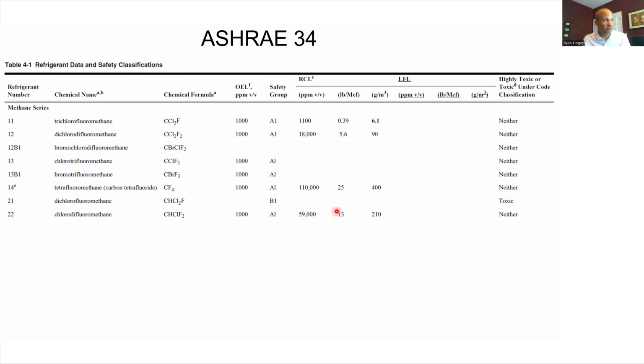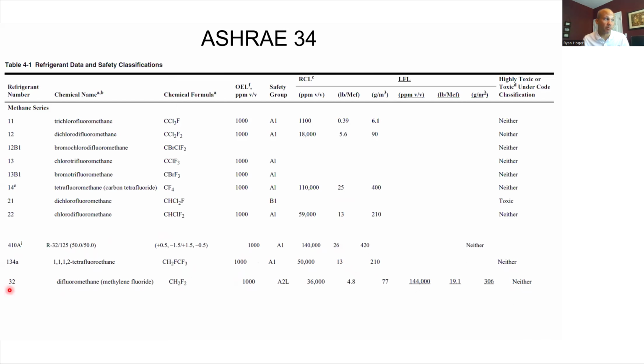So for R-22, the refrigerant concentration limit was 13. If I go to 410A, it's 26. R-410A is half as risky as R-22, if you will. If I go to 134A, it's the same as R-22. Now my first flammable one, R-32, it's listed as an A2L. I'm going to call this 5 times as risky as R-410A, and it shows up in the flammable section. And most of the R-32 extra risk is because of the flammability. It's not really that much more toxic than R-410A. It's because it's more flammable. If we add R-454B, I'm going to call that 8 times as risky as R-410A.